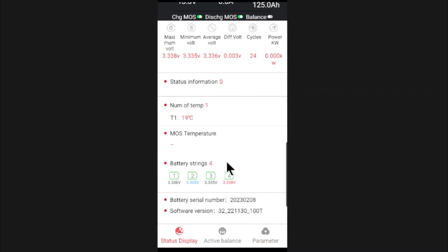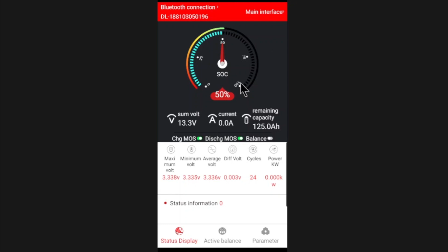You can see on the front display that the state of charge is set to 50%. Once we charge it all the way up, it will trigger the high voltage disconnect, then automatically set the state of charge to 100%, making it more accurate. But you've got to take the state of charge with a grain of salt—most of these BMSs are close, but not 100% accurate.